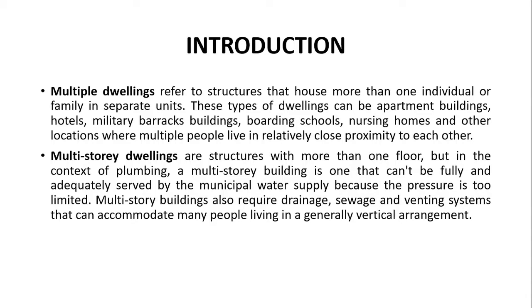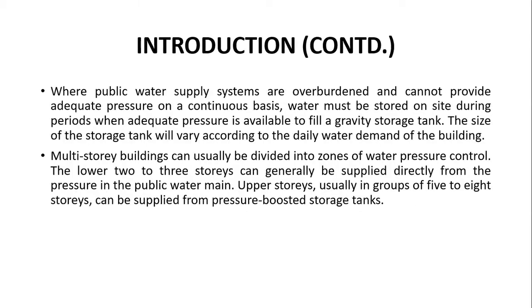Multi-story buildings require proper drainage, sewage, and venting systems to accommodate the many people living in a generally vertical arrangement. Where we have public water supply systems, they can be so overburdened supplying such a large area that they cannot provide adequate pressure on a continuous basis. So water must be stored on-site during periods when the building can receive adequate pressure to fill a gravity storage tank, and the size of that storage tank will vary according to the daily water demand of the building. We divide multi-story buildings into different zones according to water pressure and its control.